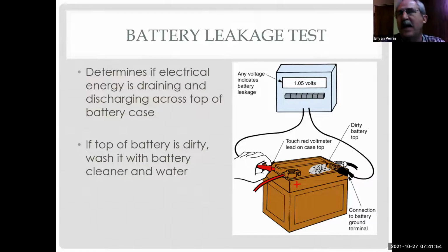In the old days, when all batteries were dirty because they leaked water and were not maintenance free, and they all had acid on them, if you put them on concrete, they would go dead because the concrete would make the electrical connection and the battery would discharge. On modern batteries, since they should never leak, I can put them on the ground all I want. Matter of fact, a lot of times we actually store them on the ground. It's a non-issue. There's nothing magic about it, but the old thought was that the ground pulls the energy through the case, so people thought you needed to put it on a piece of wood.